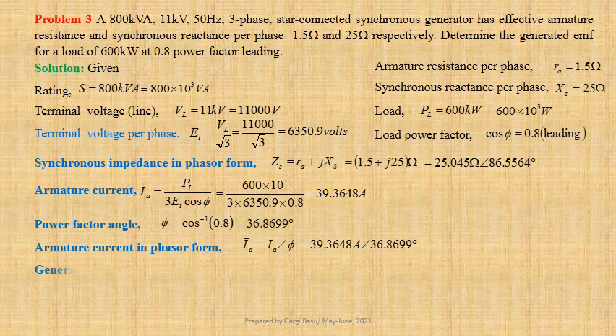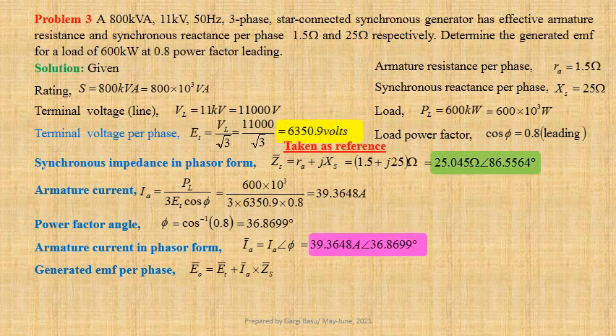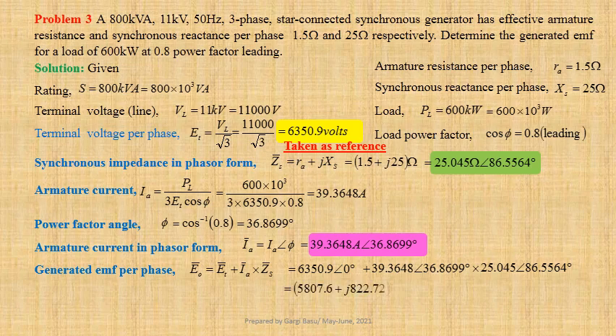Expression for generated EMF per phase E0 equals ET plus IA into Zs. Taking ET as reference, we get E0 equals 6350.9 at an angle 0 degree plus 39.3648 at an angle 36.8699 degree into 25.045 at an angle 86.5564 degree. That gives us 5807.6 plus j822.72 volts.